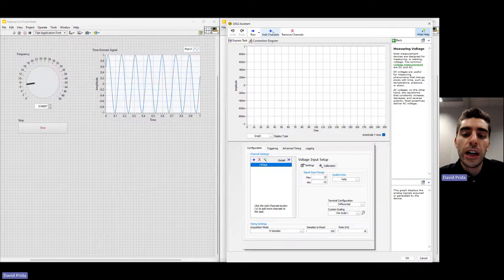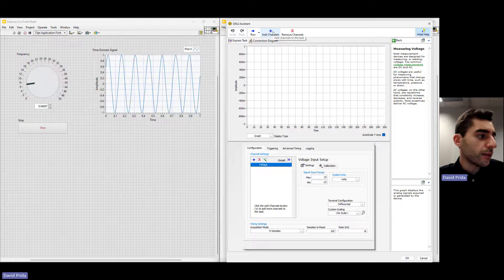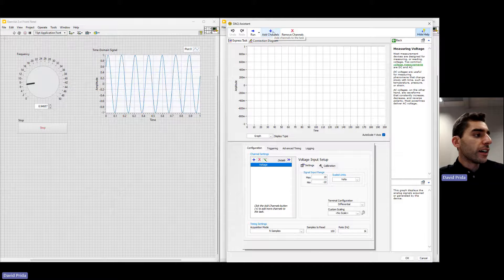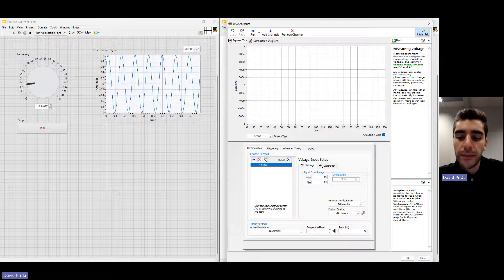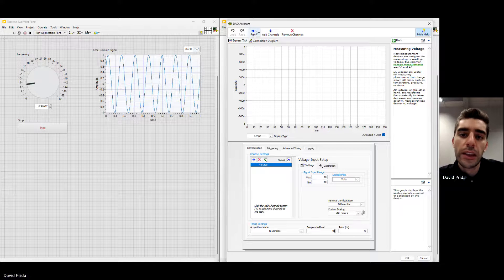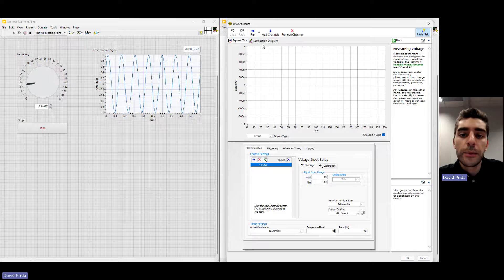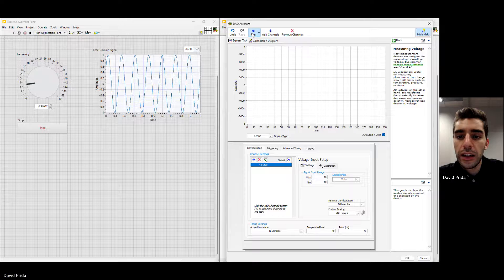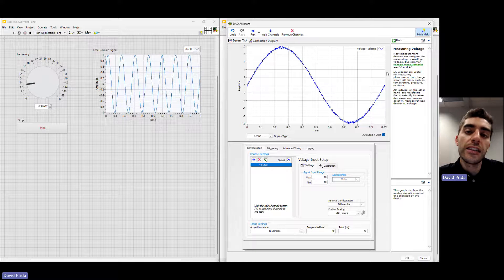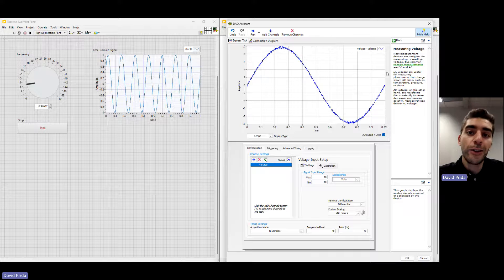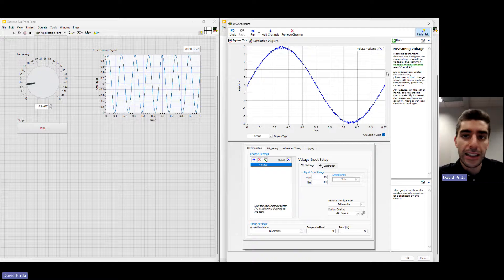That opens up more settings for our DAQ Assistant. We're going to change the timing settings — changing the samples to read to 1000, and leaving the rate at 1000. If I hit Run in this test panel, I can quickly see some data. We can see a simple sine wave, which is what these simulated devices generate. If I was using a real device, it would acquire real data, but the setup is exactly the same.